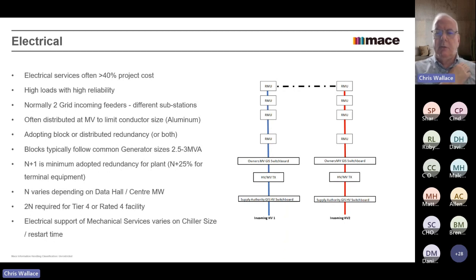So it may be that you consider this as one of these would represent a ring main unit, maybe one data hall, and the data halls, depending on the size and the capacity of the data hall, you might have two on one floor, or one on one floor, or more than one on one floor. So really these are just the building blocks. And as I said before, this is not what one particular company does. This is what I found, with variations, over 10 years; most of the customers that we've been doing have been doing something like this.